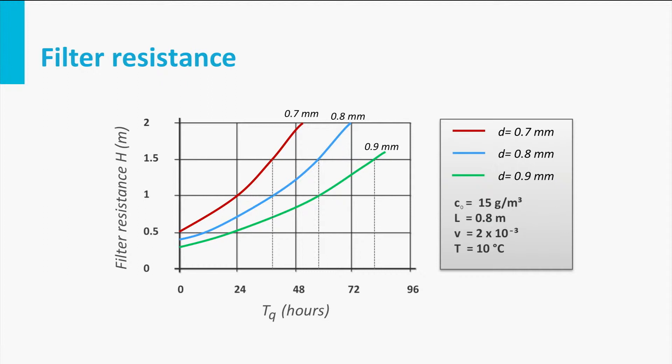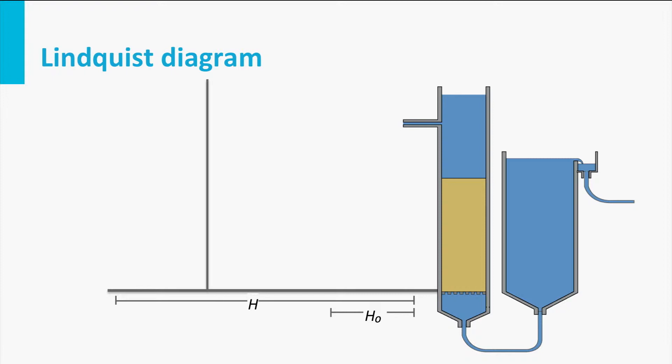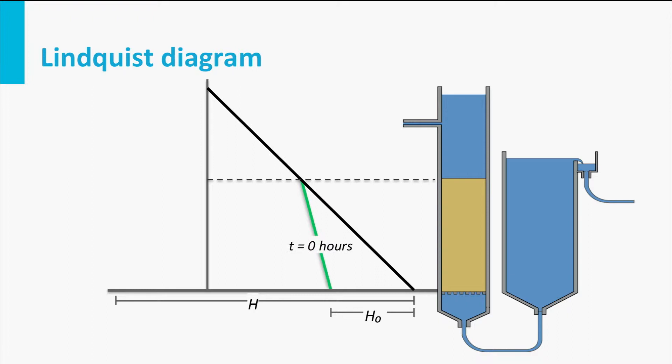The maximum allowable head loss is determined by the filter bed height and the supernatant water level, as observed in the so-called Lindquist diagram. When water is not flowing, the total pressure at the bottom of the filter is equal to atmospheric pressure plus the pressure of the water column in the filter. At the start of a filter run, clean bed resistance occurs and the pressure at the bottom is slightly decreased.